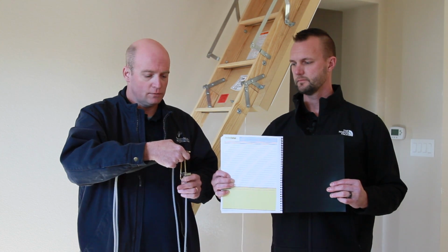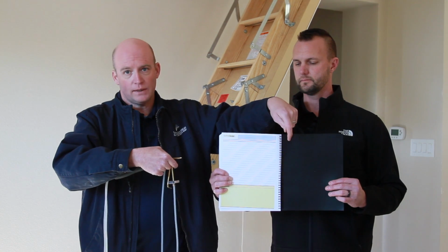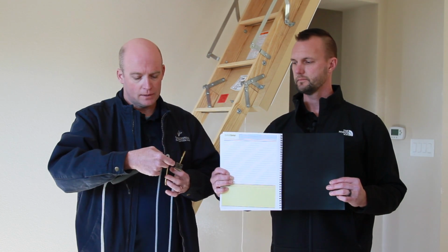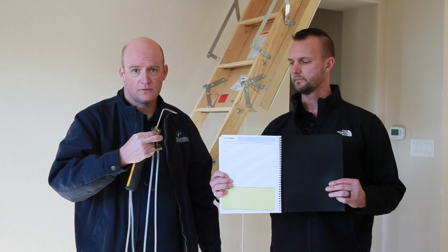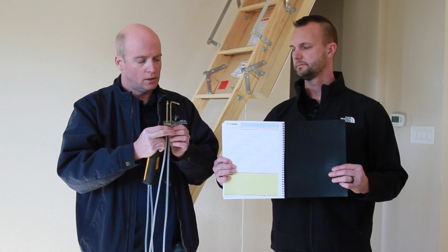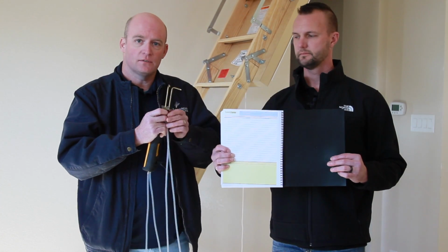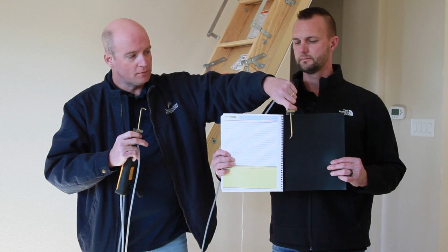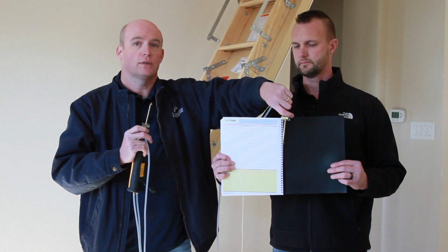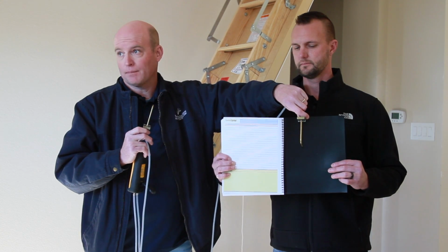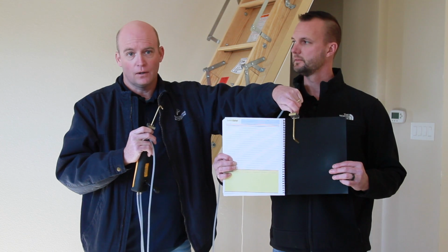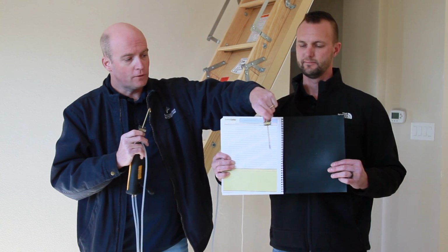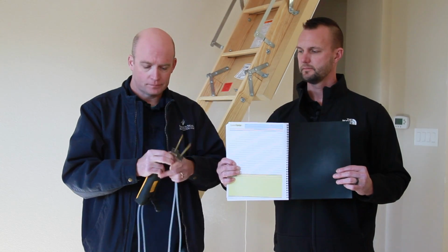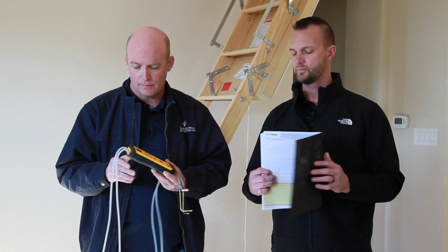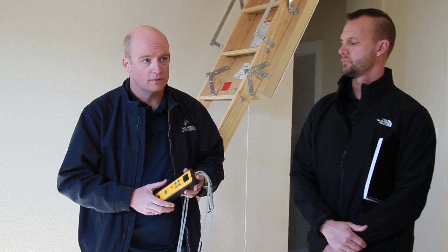But the critical and most difficult reading to get, we need a hole between the furnace and coil. The data supplied to us from the furnace manufacturer will only provide CFM data at a certain pressure without the coil attached. It is not tested with the coil. So we have to be very careful when drilling a hole in this section. If we get too far towards the coil, what do you think might happen? We'll hit the coil. Then we're calling dispatch. We don't want that. If you go too far in, we're hitting parts of the heat exchanger. Once we have that data, we can look it up on a table that's supplied with the install manual, and it will tell us exactly how much CFM that unit is producing at that given time.